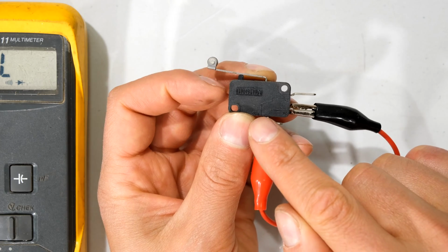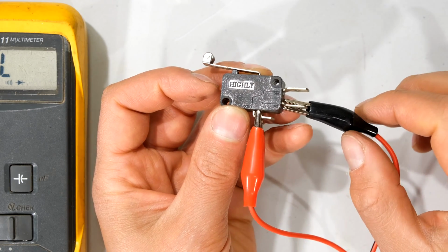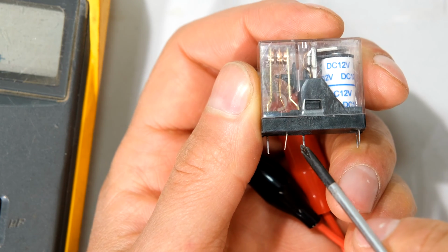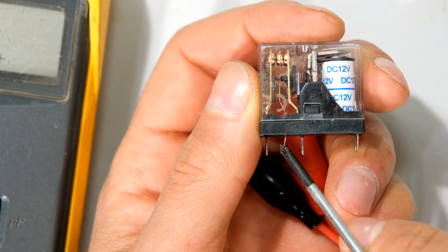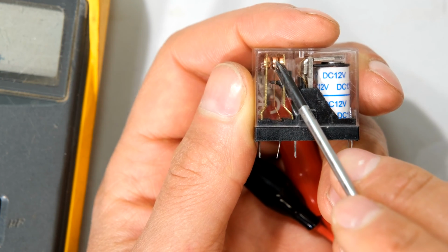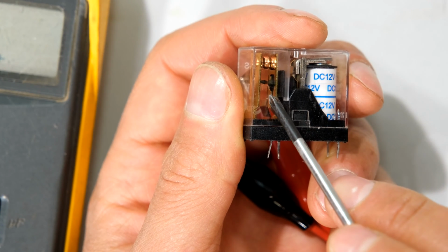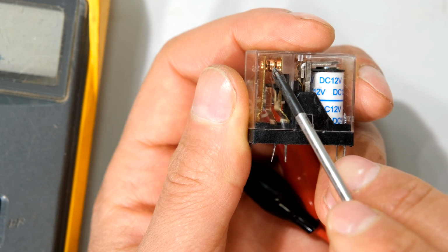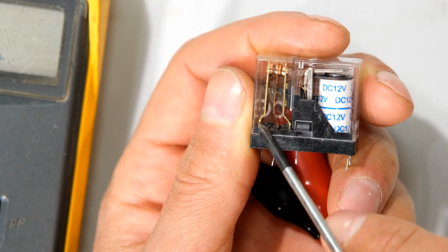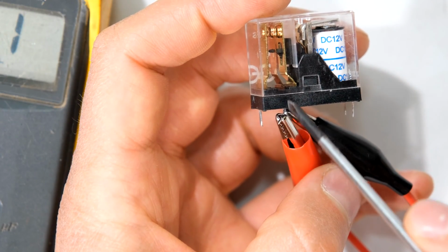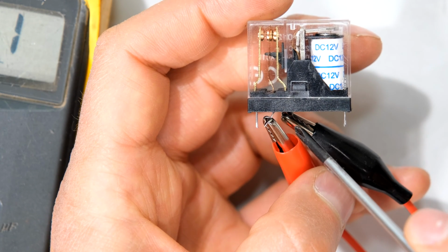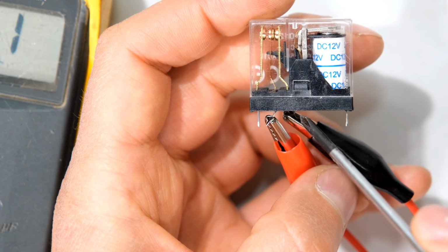And that is why the labels of normally open and normally closed are shown on the body here. Right, so here I have a relay and there's a normally open and normally closed connection. There's the common, the one in the middle. It's not always like that for all relays, but I know it's the common because this piece moves. If you look at this copper conductor that is in the middle, sandwiched between these two sides, that is the one that is moving left and right. It's either going to mate with that conductor or it's going to mate with that conductor.